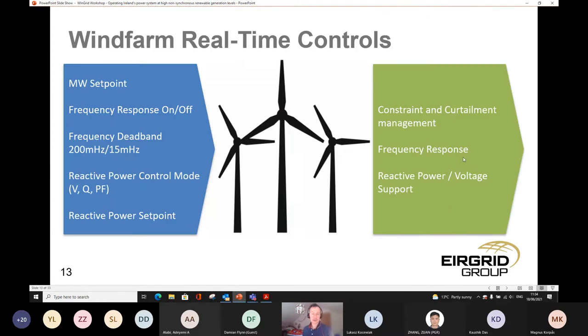So based on that output, this gives an overview of some of the controls that we have of wind in real time from our TSO control centers. This applies to any wind farm above 5 megawatts, whether transmission or distribution connected. So we can control the megawatt set point of that wind farm.